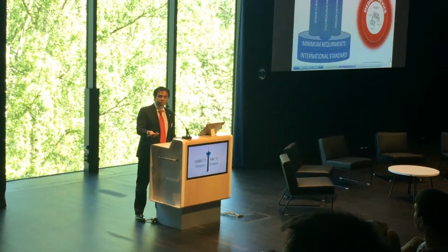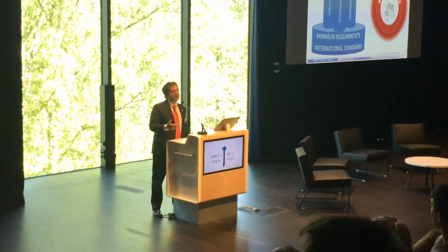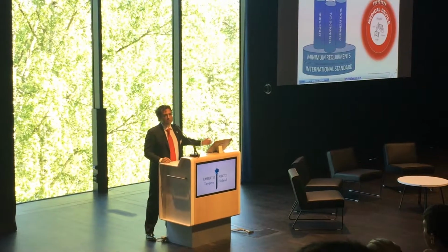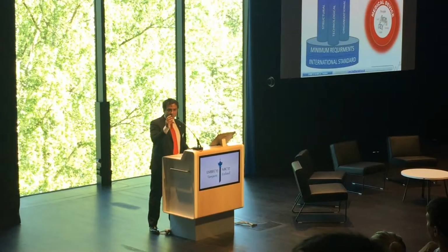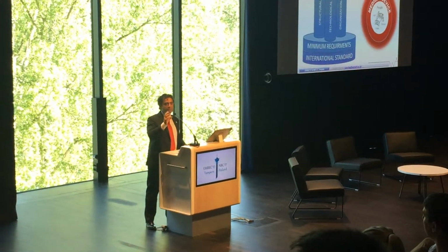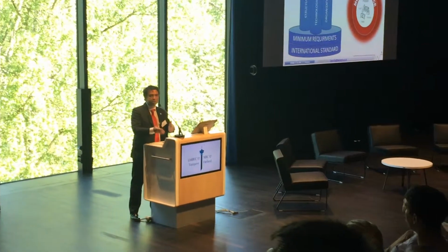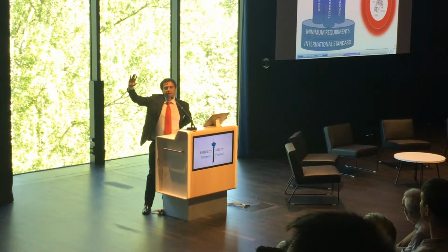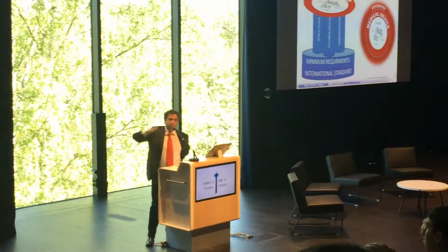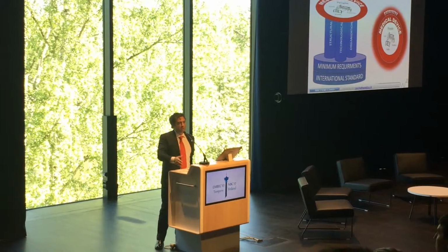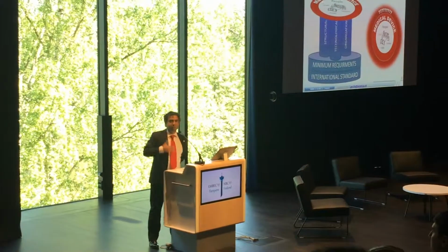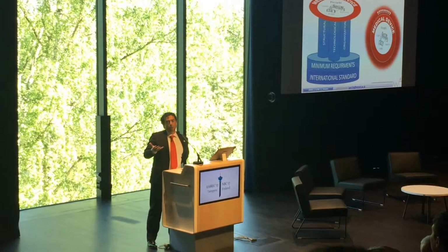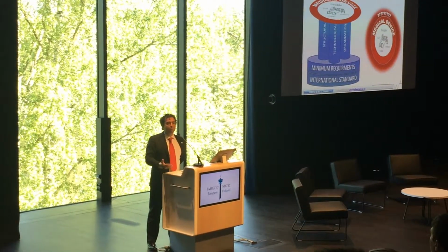And the same for infrastructure. You know that the microshock risk has to be taken into consideration if you are in a class 1 or class 2 or class 3 environment. And you know that a class 2 medical device can be operationalized only in a context in which there are those minimum requirements. In other words, this means that your medical devices, we know they depend on the users, the patient, even the relative of the patient who entered the hospital for a visit, but they are based on those pillars. What happens when those pillars are questioned?